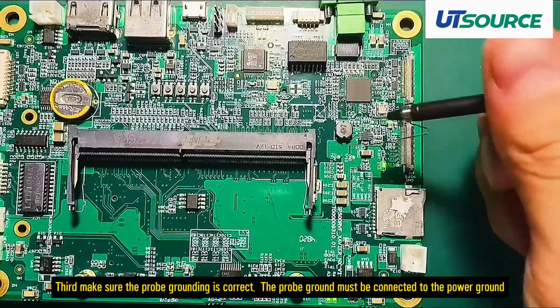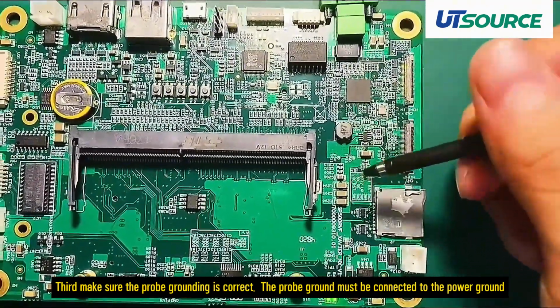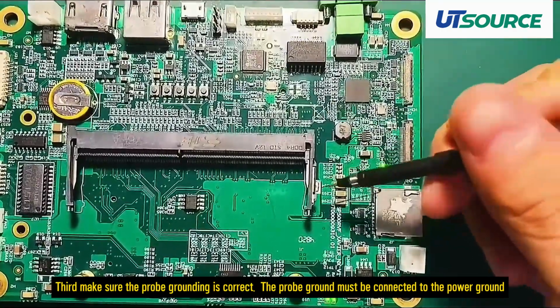Third, make sure the probe grounding is correct. The probe ground must be connected to the power ground.